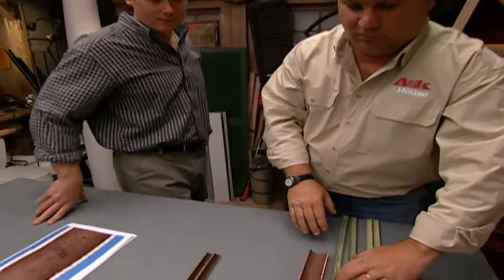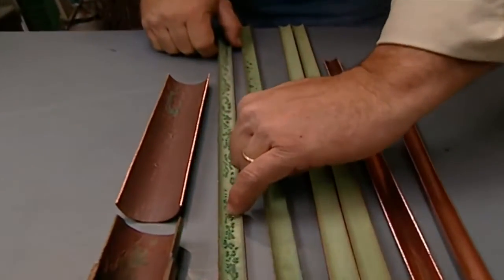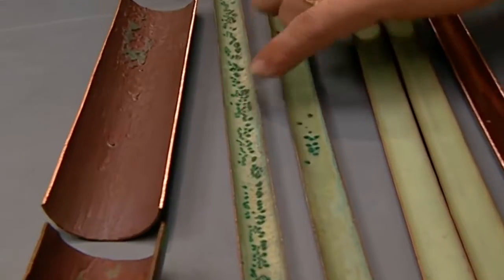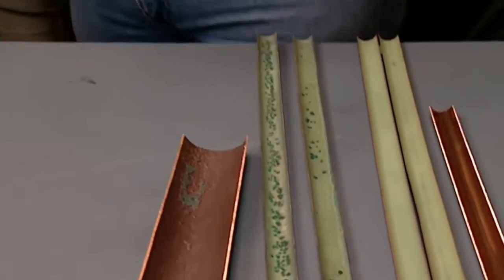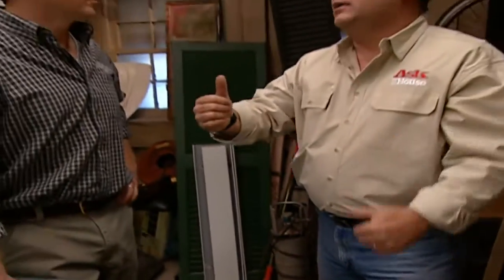What do we do about it? Well, on the water heater, on a new installation, if you can change that anode rod every 3 to 5 years and stay on top of it, you can get a water heater to last a long time. If it's been more than 10 years, don't even bother with the water heater. If it's on the cold water side, you see pit corrosion, you would suspect flux. So the pit point here. So you really have to decide is it on the hot or the cold. If it's on both, have your water tested.